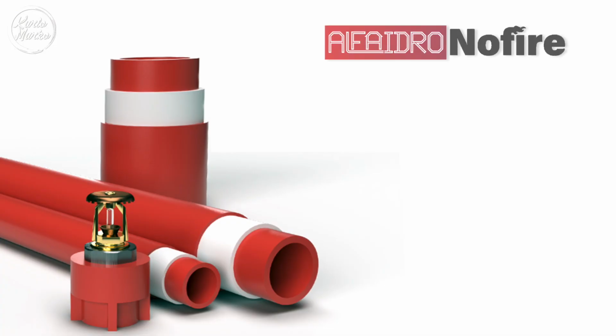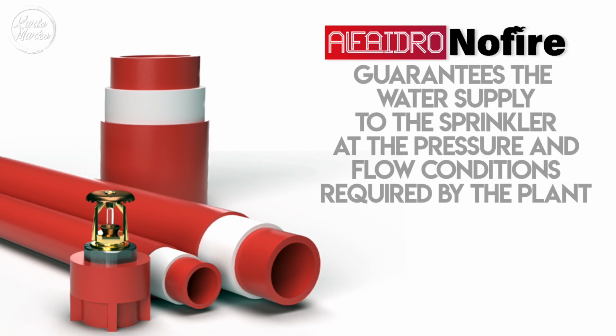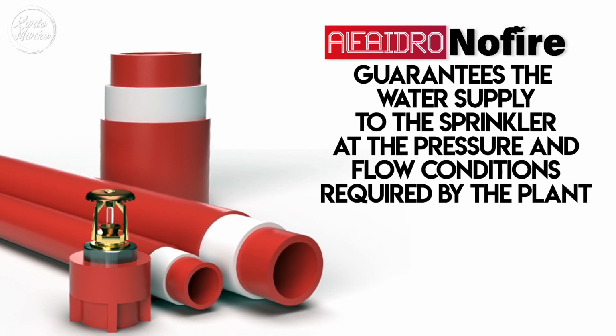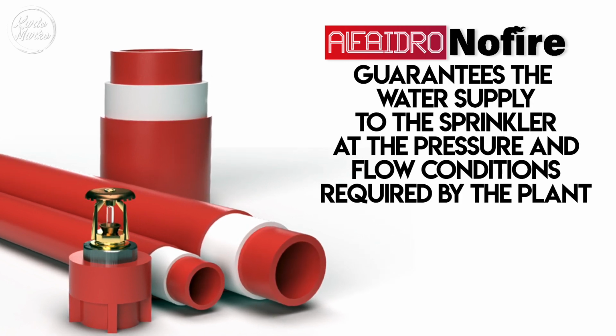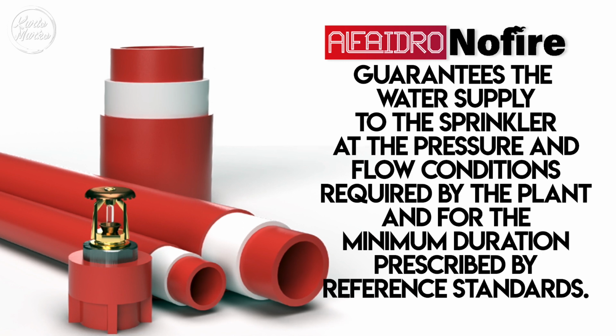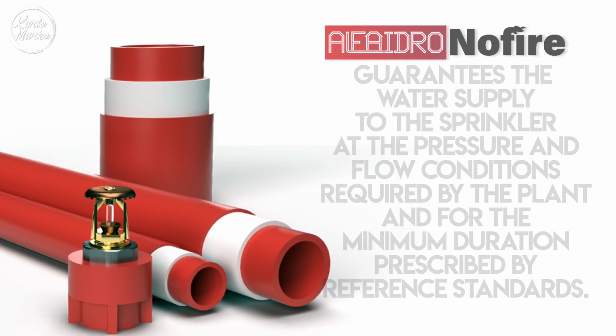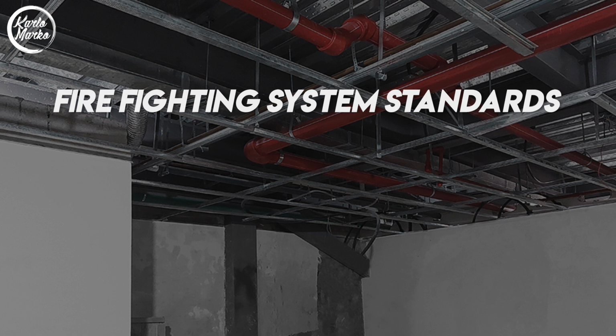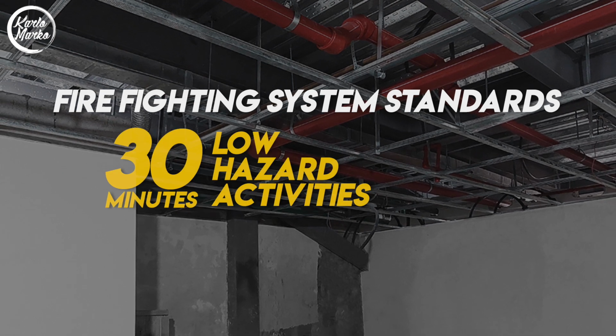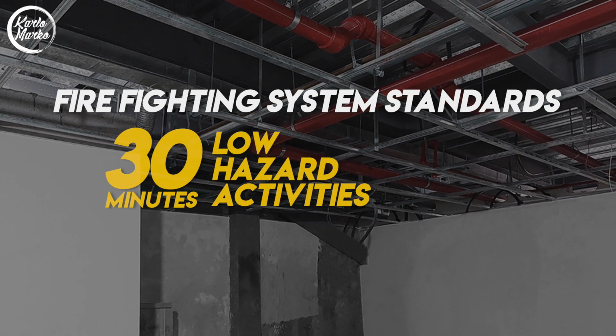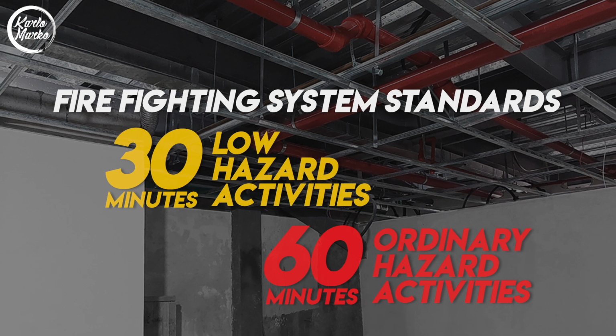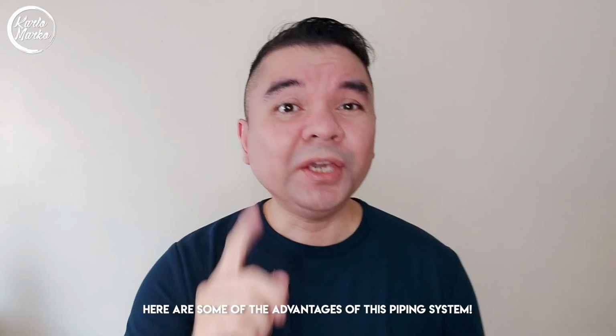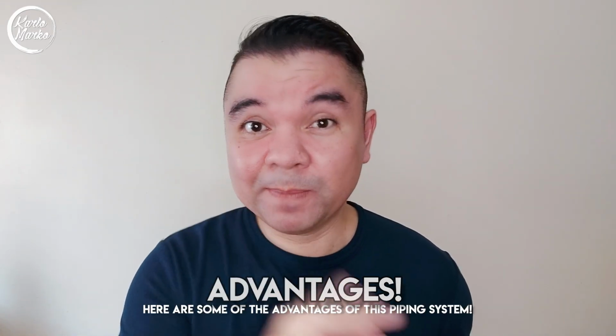The Alfaidro No Fire system guarantees the water supply to the sprinkler at the pressure and flow conditions required by the plant and for the minimum duration prescribed by reference standards. This is according to the firefighting system standards, which is at 30 minutes for low hazard activities and 60 minutes for ordinary hazard activities. Here are some of the advantages of this piping system.